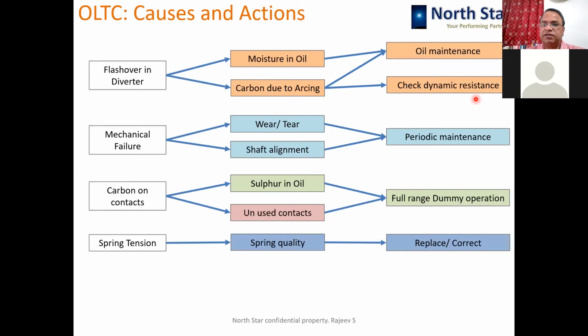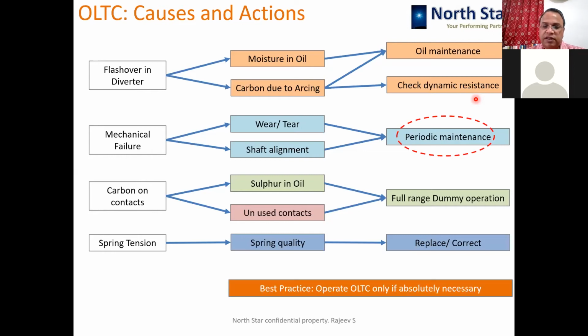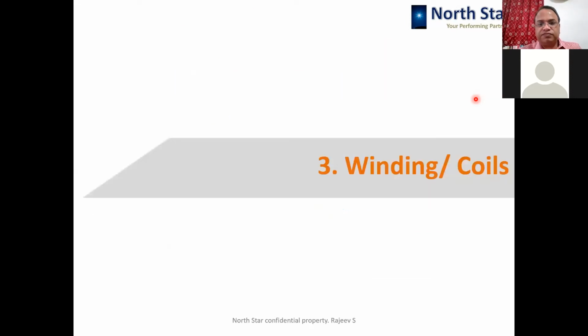The OLTC maintenance has to be done as per the schedule based on the number of cycles specified by the OLTC manufacturer. Like your four-wheeler or two-wheeler, you follow the maintenance schedule based on kilometers; here it is the number of cycles which is to be respected. Best practice, if I suggest, is to operate the OLTC as little as possible, only if it is absolutely necessary. So keep your AVR settings at a wider band, so that the OLTC is not operating unnecessarily quite often.